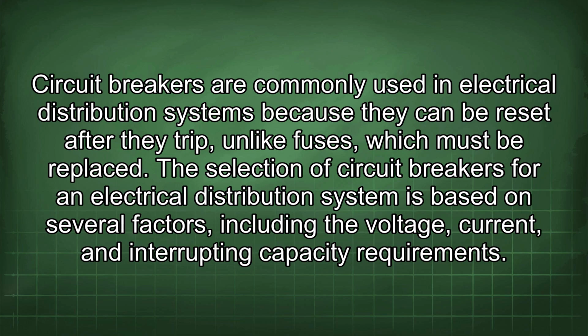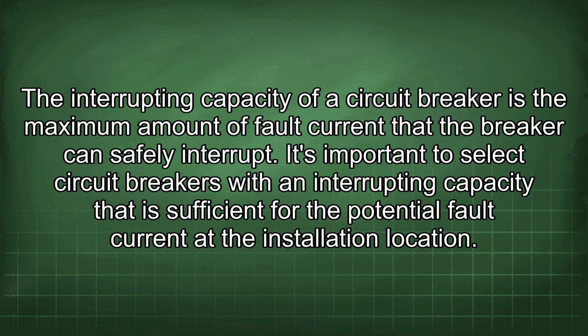The selection of circuit breakers for an electrical distribution system is based on several factors, including the voltage, current, and interrupting capacity requirements. The interrupting capacity of a circuit breaker is the maximum amount of fault current that the breaker can safely interrupt. It's important to select circuit breakers with an interrupting capacity that is sufficient for the potential fault current at the installation location.